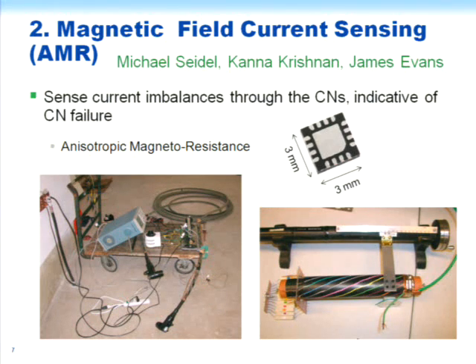And also, if you look closely, you'd find that in the process, I guess, of installation and removal, some of the concentric neutrals have bunched up in locations and so on. But I think this is probably a typical case. So here's the device that moves the magnetic field sensor along the cable, and these are the standard fittings that go on the ends of a length of cable.